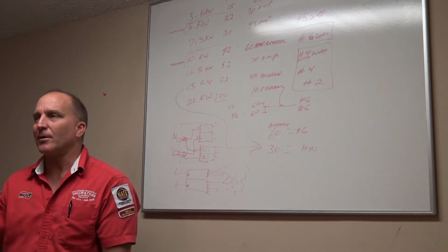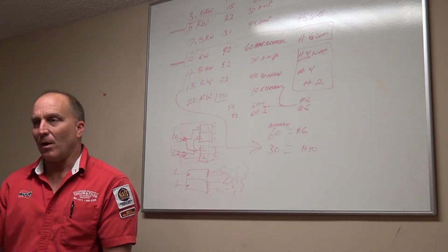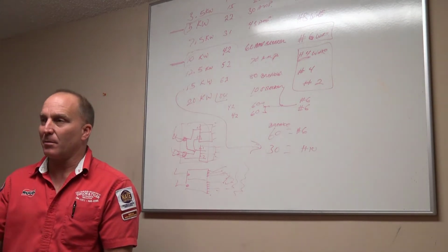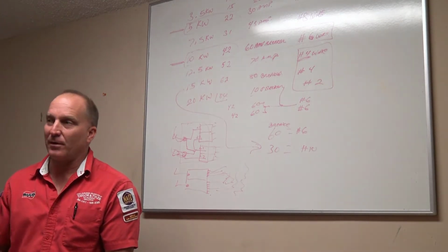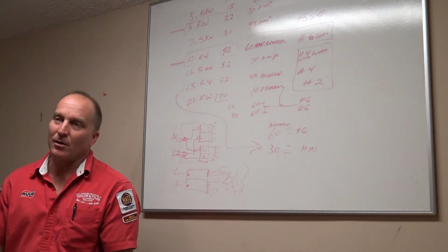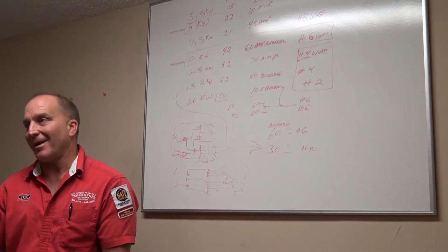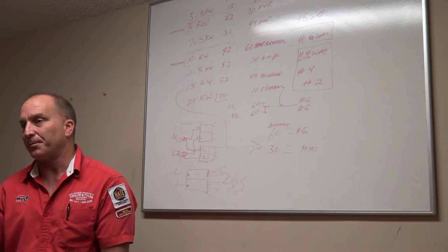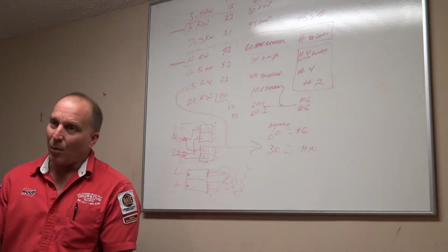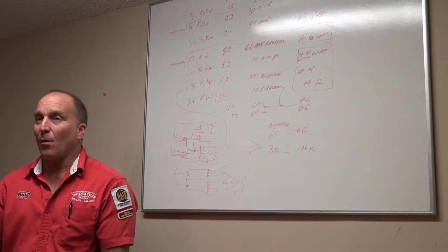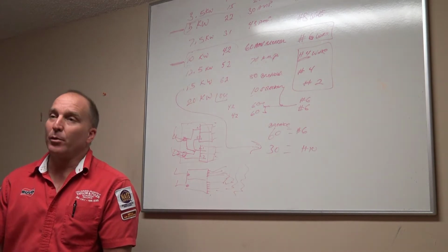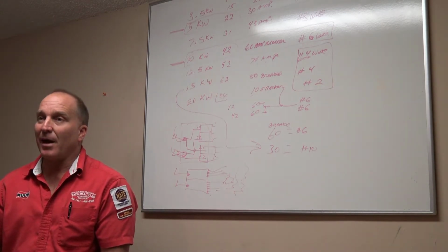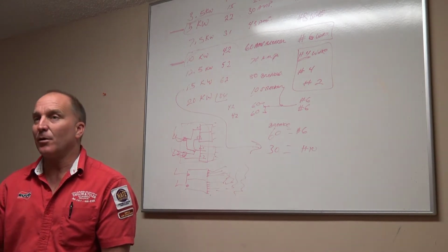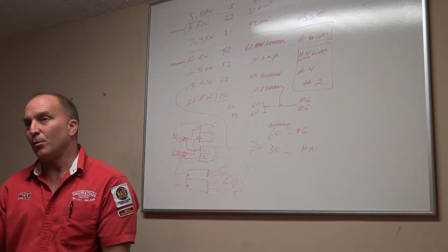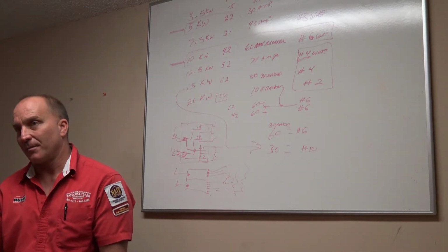All your blower wires are off on the system. Well, now you've got to look at them and go, what color are my wires? It's 220 volt, 115 volt, whatever. What color wires do I have? And I'm going to tell you, if it's a 110 volt system, your white wire is going to be your common wire. Your black wire is high speed. Your blue wire is going to be medium high. Your yellow is going to be medium low, and your red is going to be low. Your 2 brown wires go to your capacitor.